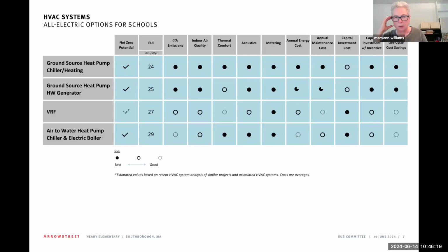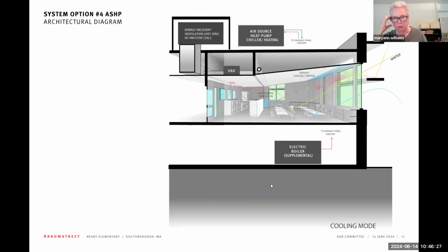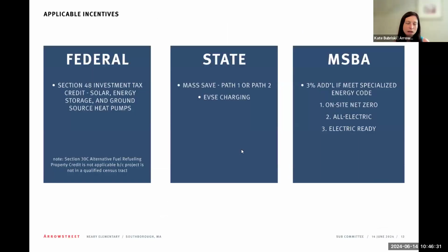Is there a sense about what size the well field would need to be if we proceeded with geothermal? Has there been any thermal conductivity testing? We don't have thermal conductivity, but we looked at both. Katie, there are two enrollments, right? 310 and 610. So for the lower enrollment of 310, we think it would be somewhere around 40 wells, and the higher enrollment would be about double the number of wells. That's anticipating fairly shallow wells, around 500 feet deep. If they were deeper wells, there would be fewer wells. You said 1,000 foot wells, right? 500 foot wells.